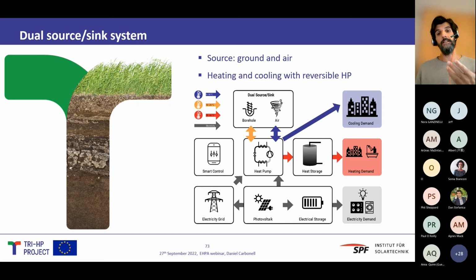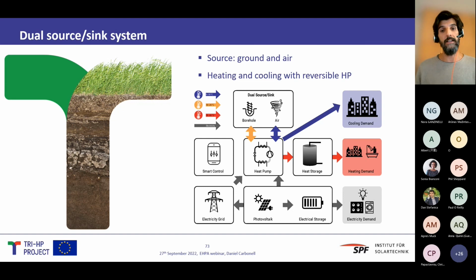The innovation here is that it has an evaporator and condenser which is dual source sink, that can use both groundwater or water from wastewater or solar collectors, and air as direct heat sources and sinks for the heat pump. That's the main innovation. If you compare with ground source, having the opportunity to use air too means you can have the same efficiency while reducing the borehole length by a factor of 2, which reduces the investment cost by at least 15%.